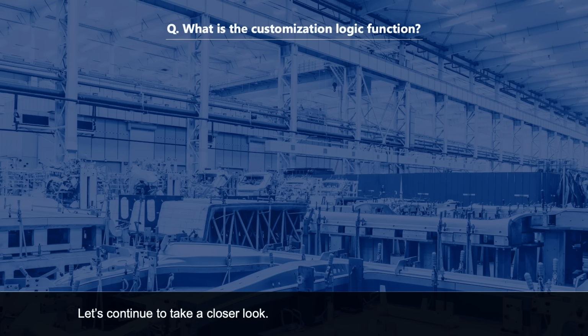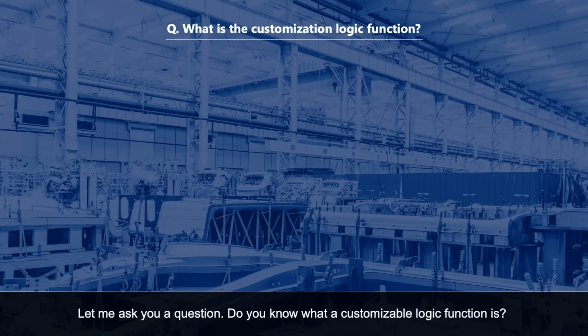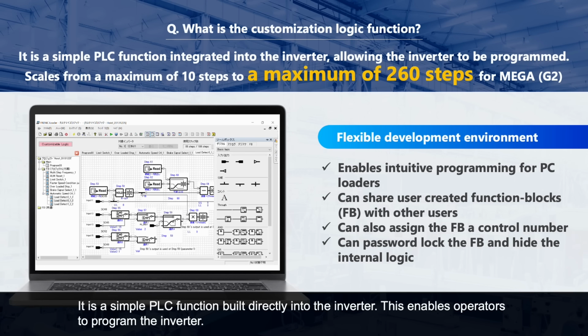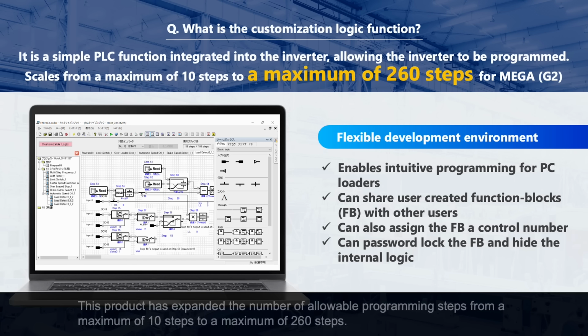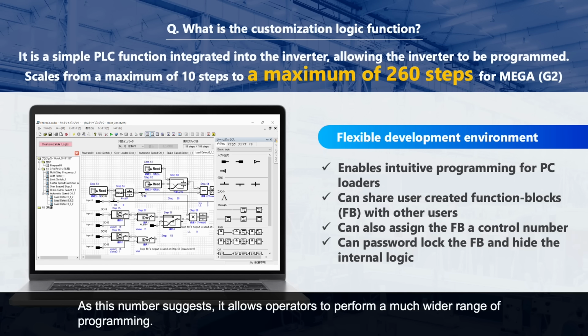Let's continue to take a closer look. Let me ask you a question. Do you know what a customizable logic function is? It is a simple PLC function built directly into the inverter. This enables operators to program the inverter. This product has expanded the number of allowable programming steps from a maximum of 10 steps to a maximum of 260 steps. As this number suggests, it allows operators to perform a much wider range of programming.